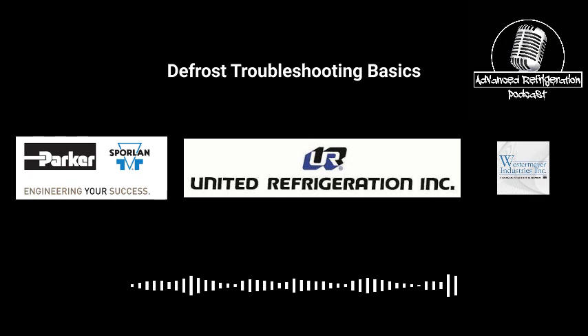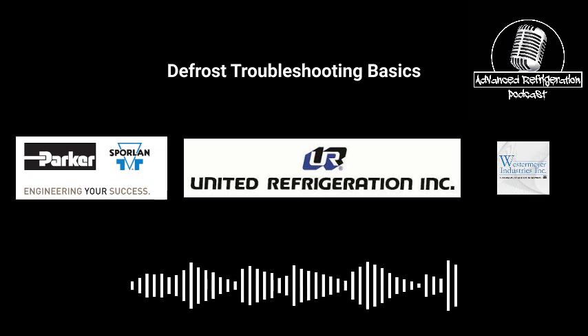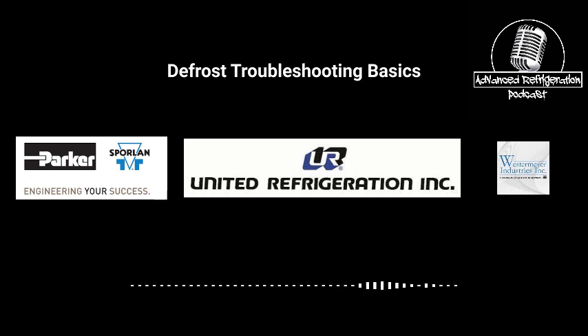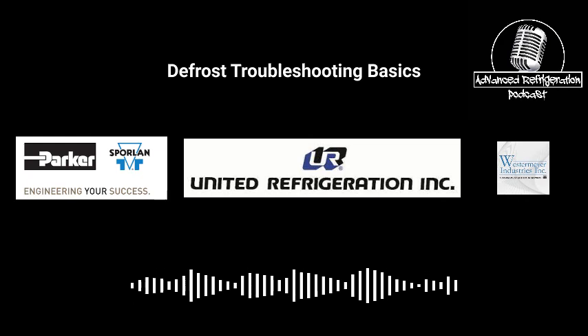That's a problem. So if anyone's ever pumped down a system out here, and I'm sure all of you have, it takes 5, 10, 15 minutes before all that liquid from the liquid line all the way back at the rack, if you were to shut that ball valve off just by letting it pump out naturally, it could take upwards of 15 minutes, right?